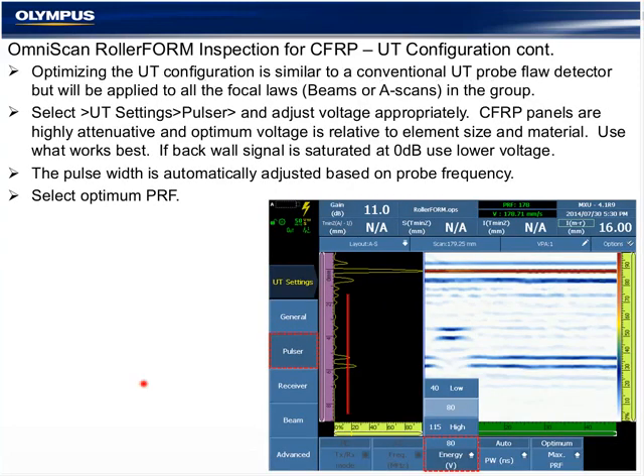So we're now in synchronization on echo or A-scan synchronization mode. We have built the group, which is the sum of all of the focal laws in the S-scan and make up the group 1. This is a single group application. And now we're moving on to the UT configuration. Most of the UT parameters are very similar to a single channel conventional flaw detector in that what we do to one applies to all of them.